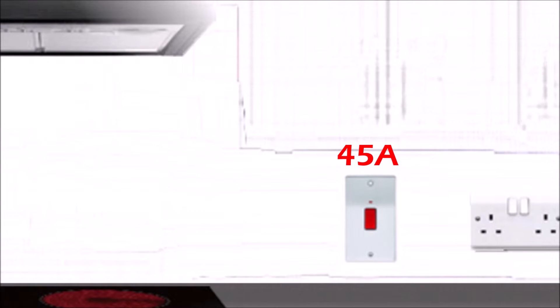So let's start with the cooker circuit. Somewhere above the worktop in an easily accessible place, you should install a 45 amp double pole cooker switch. There's a wide range of cooker switches in shops — you can have the long one with a vertical back box, the small one, or even one with a single socket on the side. Whichever you choose, the most important thing is it must be 45 amps rated.